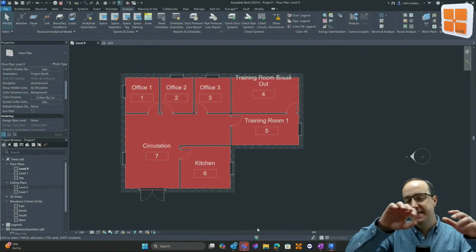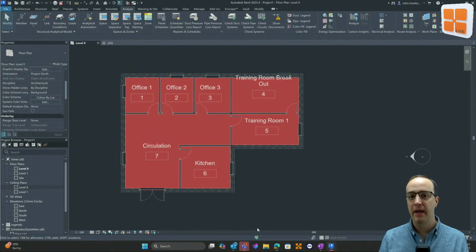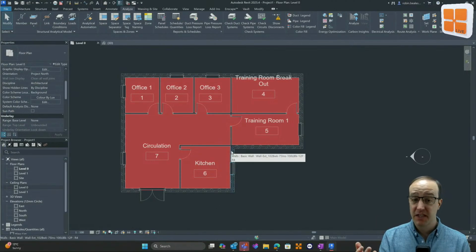And instantly my entire model highlights in red. Why? Well, because I've got no lights. There are no lights defined in my rooms and spaces, therefore it's not picking up on any lux levels. It's not going to take the windows into account. This is only from photometric lights inside of Revit. But you can instantly see what this is doing, which is actually pretty cool.